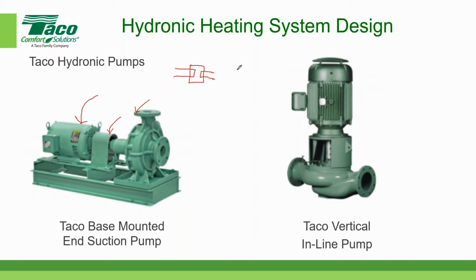Brett has a great presentation that he does, which shows the fundamentals of pumps, and he goes into the detail of how these couplings work and the concept of the shafts and stuff. The important thing to keep in mind is that a base-mounted pump, regardless of what style it is, does need to be field aligned, and it has to be done within 5/1000ths of an inch in terms of the alignment. The second major category of pumps, probably the fastest growing category, are called vertical inline pumps.